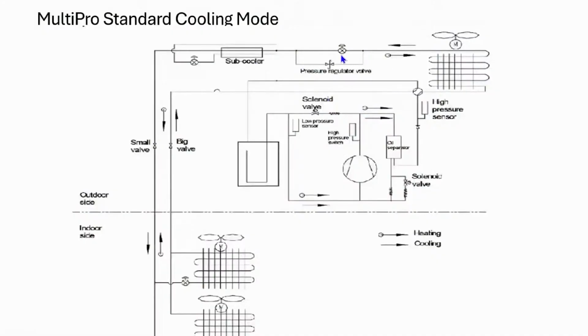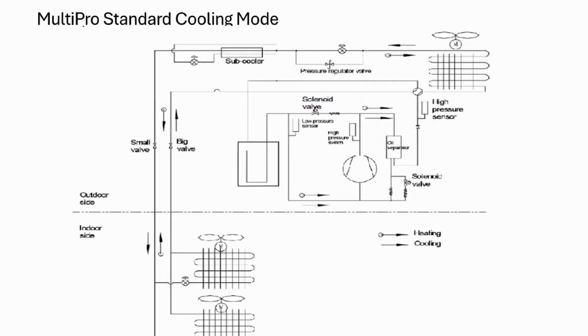Let's say I've got a system that's intermittently giving compressor error codes. But as the technician, every time you go out there, and let's say this piping diagram shows 2 indoor units, let's say we've got 4, you never get it to duplicate the issue while you're there. But every time you go there, you reset the error code, whatever the compressor error code may be, and you start up the system and bring on all 4 indoor units.